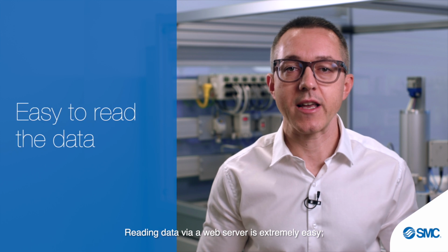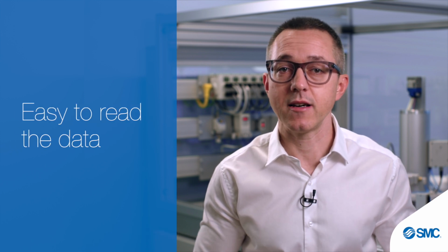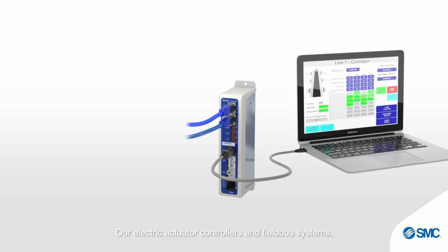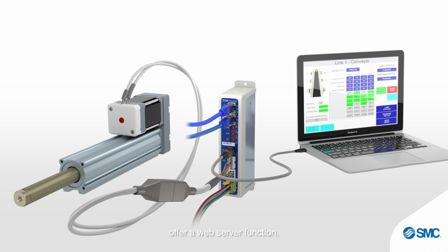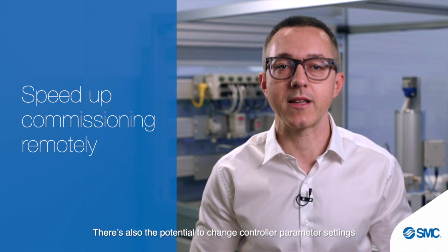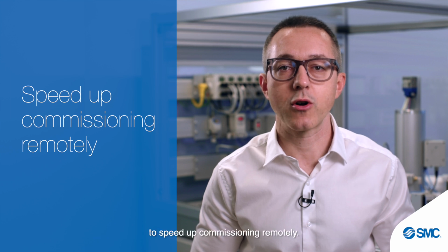Reading data via web server is extremely easy, requiring only a standard PC with a network card. Our electric actuator controllers and fieldbus systems offer a web server function. In terms of electric actuator controllers, the most important data to read via web servers are speed and torque values. There is also the potential to change controller parameter settings to speed up commissioning remotely.